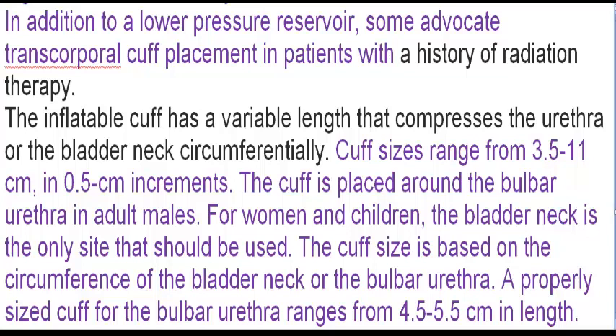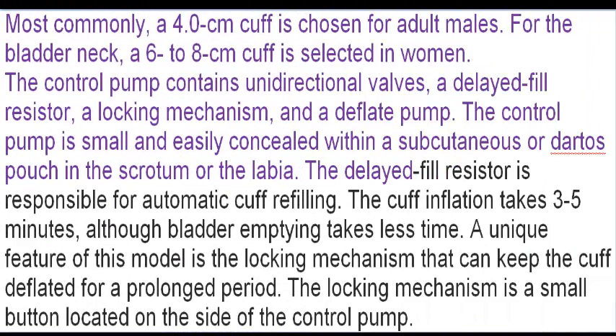Cuff sizes range from 3.5 to 11 cm, in 0.5 cm increments. The cuff is placed around the bulbar urethra in adult males. For women and children, the bladder neck is the only site that should be used. The cuff size is based on the circumference of the bladder neck or the bulbar urethra. A properly sized cuff for the bulbar urethra ranges from 4.5 to 5.5 centimeters in length. Most commonly, a 4.0 centimeter cuff is chosen for adult males. For the bladder neck, a 6 to 8 centimeter cuff is selected in women.